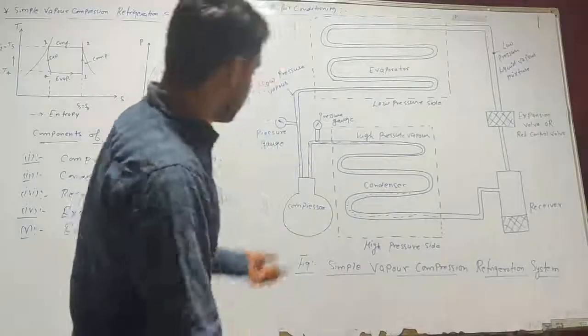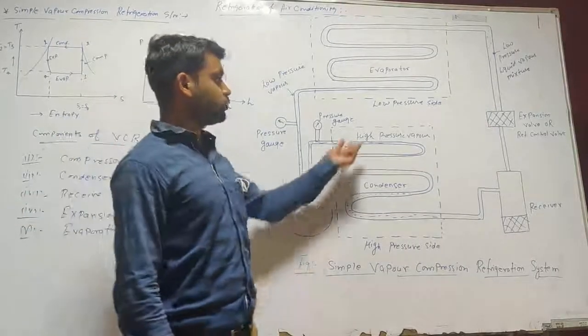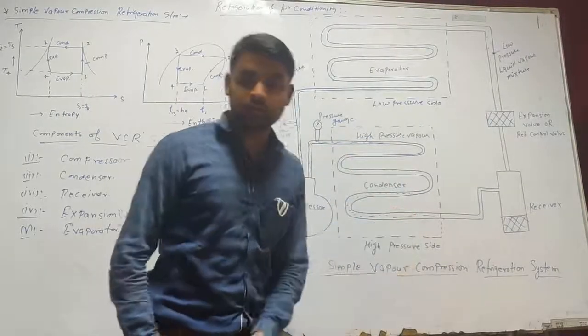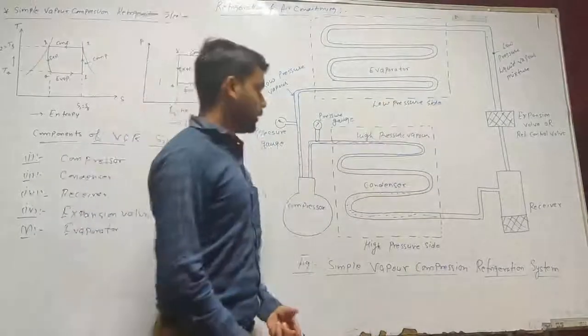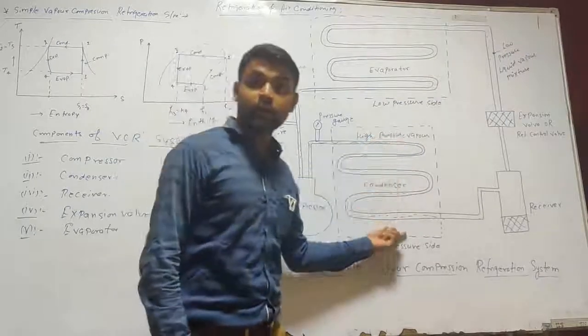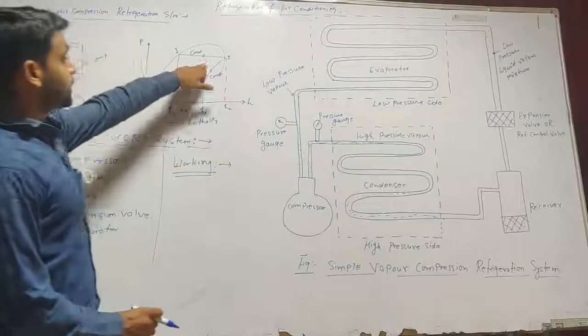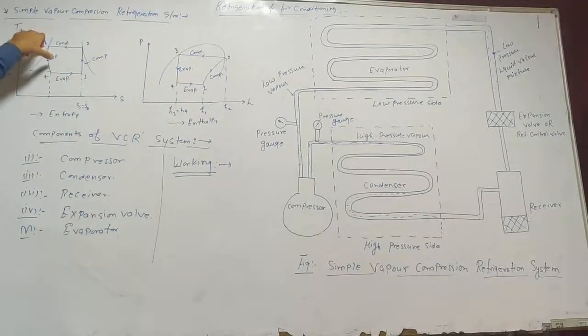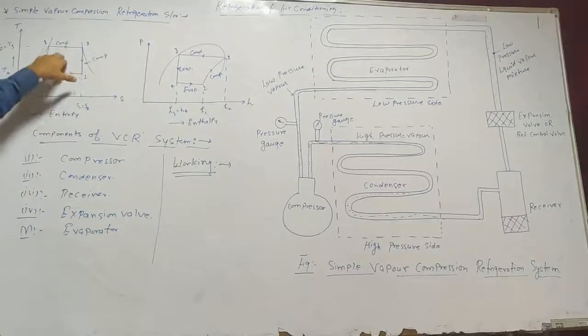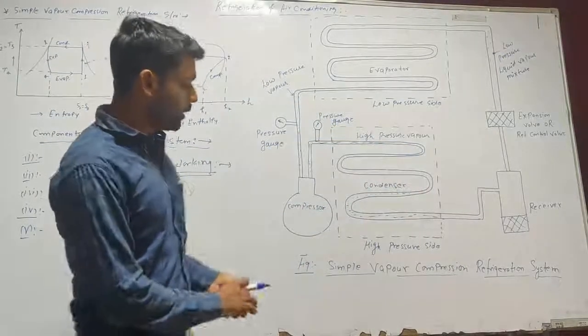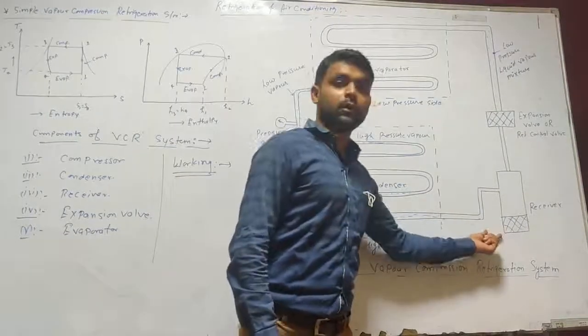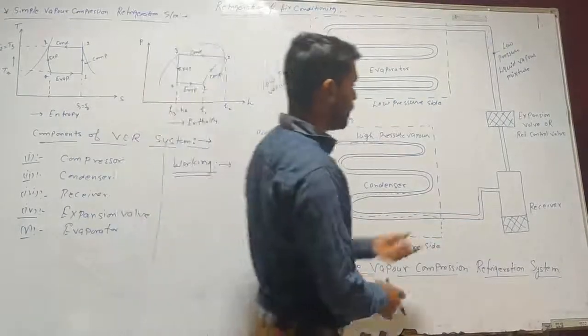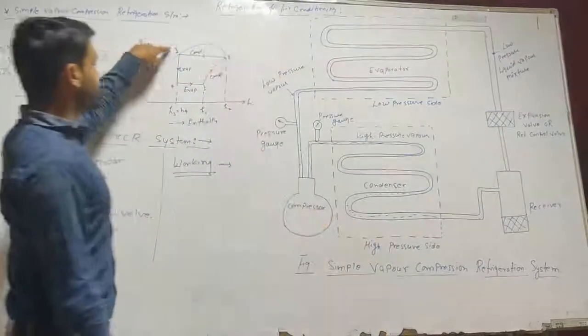From the compressor, the high pressure, high temperature refrigerant goes to the condenser. The condenser gives up the latent heat to the surroundings, and the refrigerant converts to liquid at constant pressure and constant temperature. The process from point 2 to point 3 is the condensing process. The condensed liquid refrigerant then goes to the receiver. The expansion process is from point 3 to point 4.